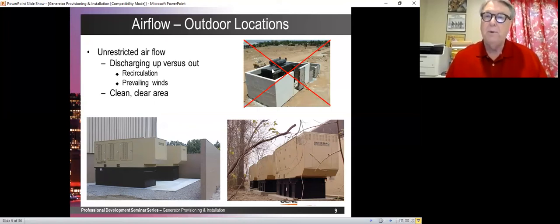By the way, up here on the upper right, even if you have upward directed discharge, you still have to make sure that you have some louvers to allow air to go in and basically not cause a high pressure inlet on the air going in. And they have done that. So inlet's fine, the outlet's got a problem. Here's a wall. For reasons that I will never understand, some people don't consider generators aesthetically beautiful. If you want to hide your generators, a wall is a very inexpensive way to do that, and it is also a very inexpensive and very effective way of reducing your noise level.